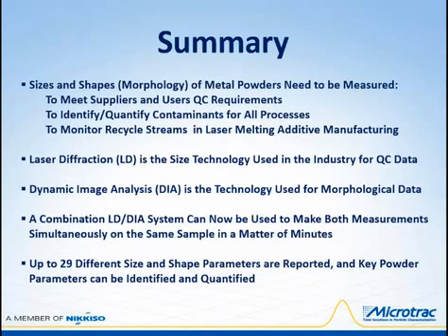A combination laser diffraction dynamic image analyzer can now be used to make both measurements simultaneously on the same sample in a matter of minutes. Up to 29 different size and shape parameters are reported, and key powder parameters can be identified and quantified.